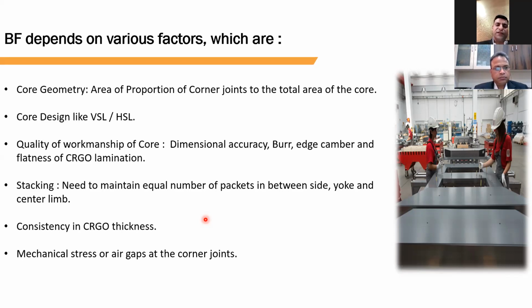If the thickness of CRGO is not uniform, then the sequence at the time of stacking will be disturbed. Even the CRGO processor can make a mistake in this area if using two different origins. Let's say you are using Chinese material and Japanese material, or more specifically, Bao make material or Nippon make material in the same job, then their average thickness will be different. If Bao material goes in the center limb and Nippon material goes in the yoke limb, they will not align properly because of the variation in thickness, and that will create an air gap.